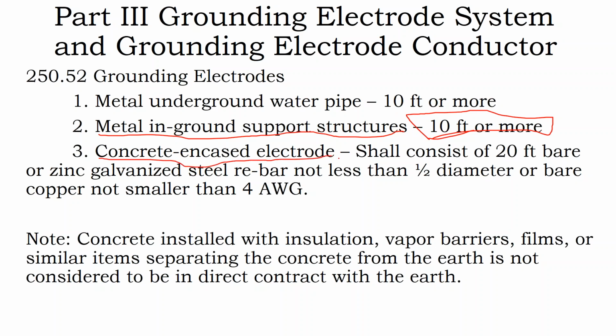A concrete encased electrode. What's common for a grounding electrode is to use the rebar in your concrete and to say that that's the grounding electrode. But the problem is that rebar has to be a half inch diameter in size. And so what's more common is you take some additional bare copper wire and just throw it down into your foundation as well. But the thing is, concrete is less conductive than normal surface dirt, your clay and sandy soils. And so instead of just having an 8-foot copper ground rod or a 10-foot metal pile, when it's going into concrete, you have to have additional material in that concrete for it to be considered a grounding electrode.